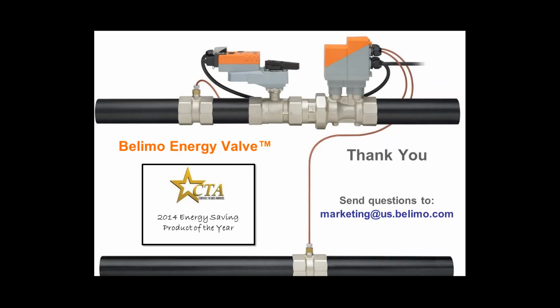Somebody said, good presentation. If you're controlling only delta T, why the energy meter? Can you define what the energy meter you mentioned? Okay, so the energy meter is just sort of a function of what this product is. The valve's electronically pressure independent, which means it uses a flow meter to become pressure independent. And then we're measuring delta T. So if I have flow and delta T, that is a BTU meter. And so it's there, we might as well use it.